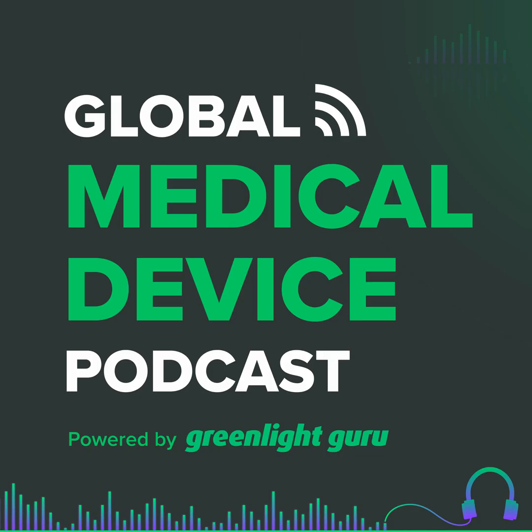I have a customer I work with. They were working pretty closely with the FDA. They got a breakthrough device designation, so they get to meet with them more often and get good feedback. And one of the things they were hearing from the FDA was about risk management, and I was helping them with risk management. It was going really good. They had a very well built out risk management. We used a lot of those different tools to really dive into what could go wrong with the device, in addition to taking the top down approach. We built it all in a 14971 format.